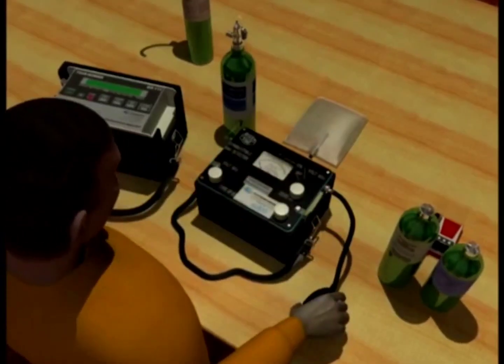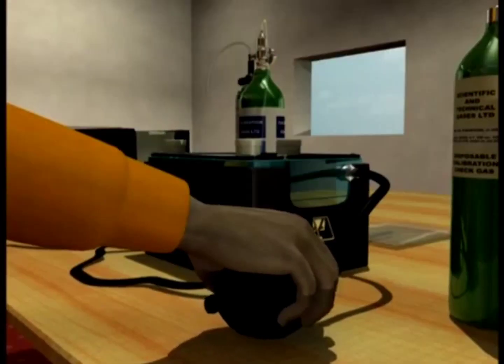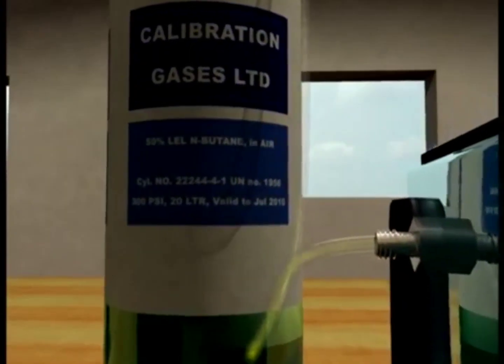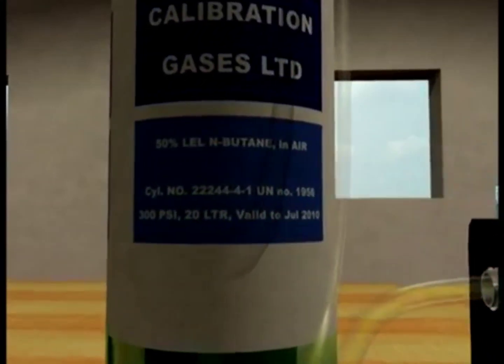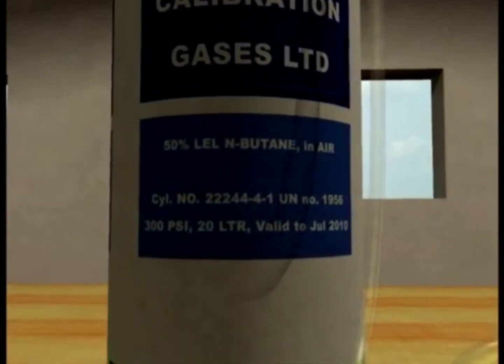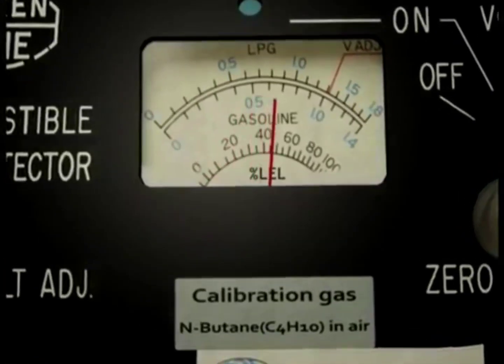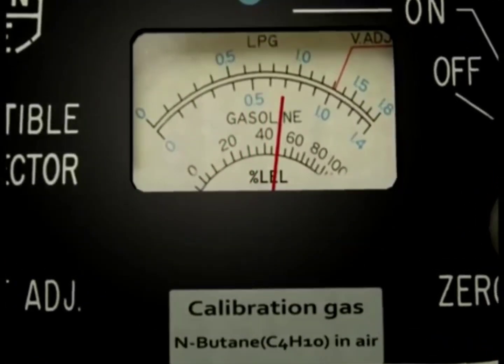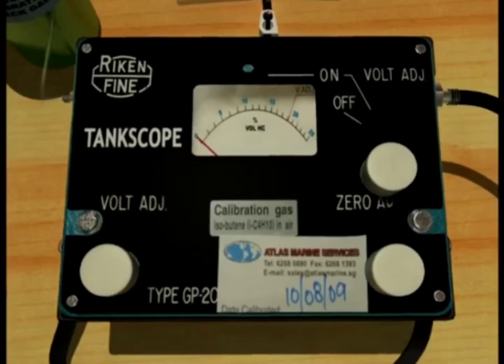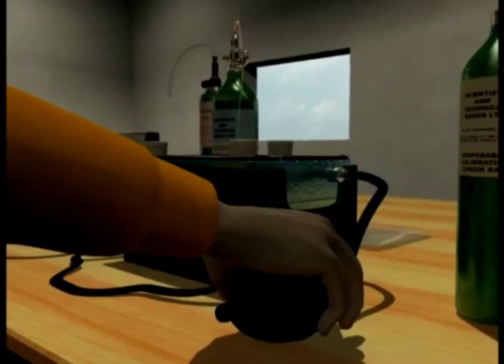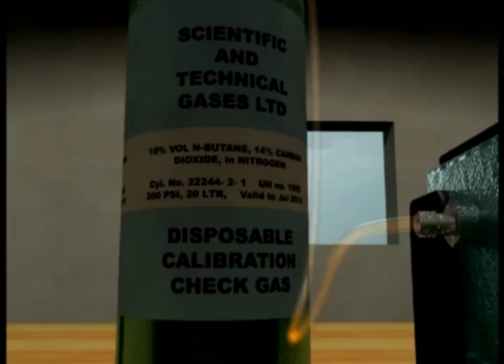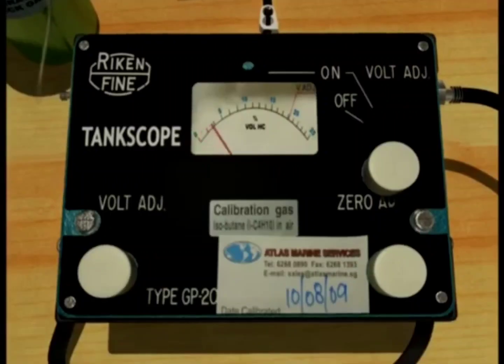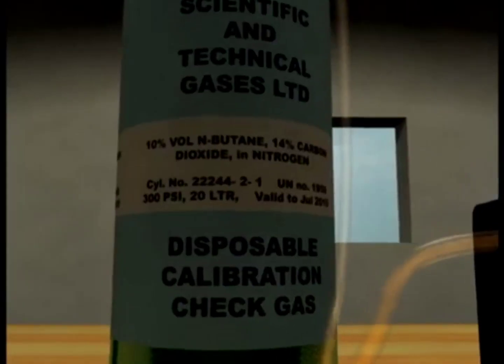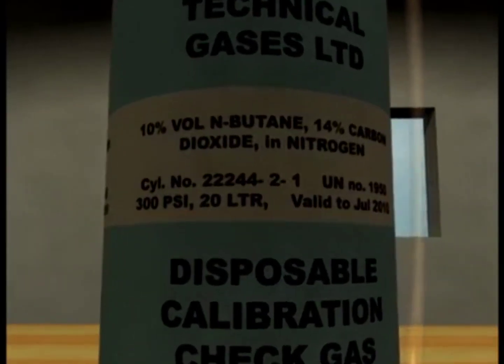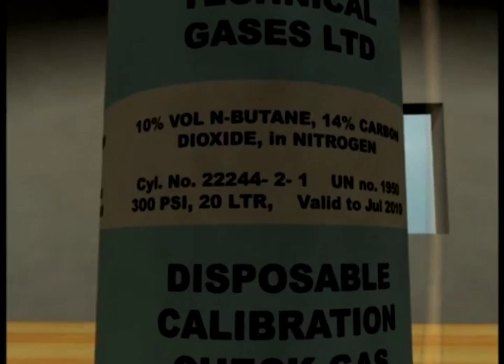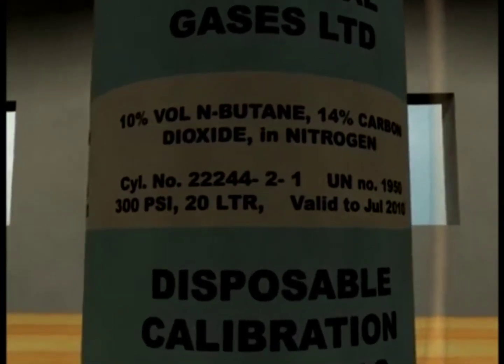Some combustible gas meters are also calibrated using isobutane in air mixture with 0.9% volume of isobutane and balance air. This would give a reading of 50% LEL on the scale. A tank scope used for detecting combustible gas in an inert atmosphere would use butane or isobutane gas with a predetermined volume of, say, 8 to 10% with balance nitrogen. The exact volume of the flammable gas present in the mixture would be marked on the label of the bottle.